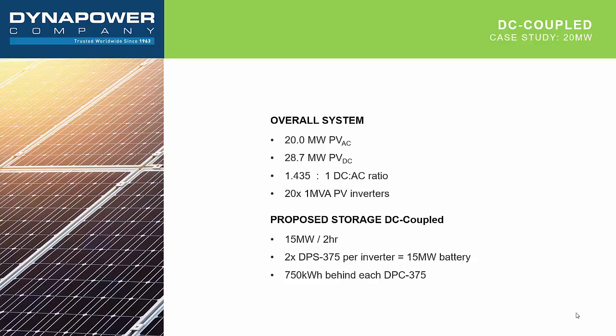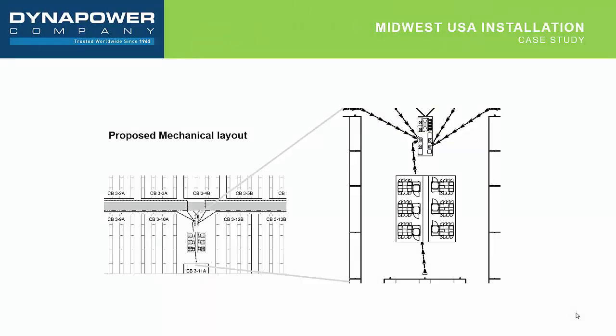Again, because this was a retrofit application, we first had to look at the physical layout. So we took the physical drawings of the site as represented on the left and did an overlay looking at whether or not the storage would actually fit. As it turns out, it did. There was a nice laydown area from the initial installation that provided space to add the storage as depicted there on the right, where you see the 4 systems.